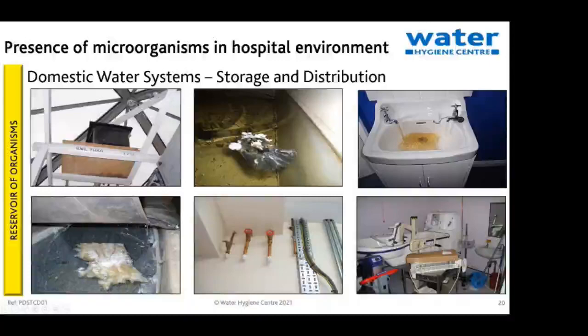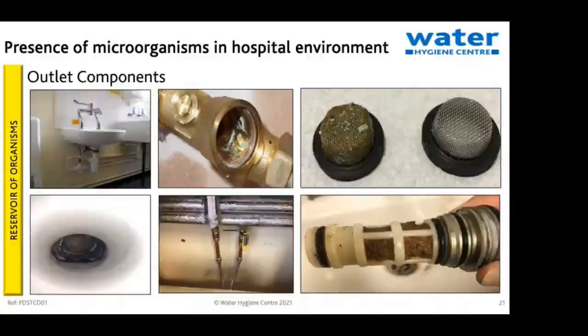So we've got areas of concern there, but that's not an uncommon practice. From a cold water storage tank, we also have hot water generators that may be undersized, not achieving the right temperatures, or poorly configured. And distribution systems with cut off ends, little used outlets, infrequently used outlets, poorly configured, gaining heat due to lack of insulation. These are all areas we come across on a regular basis.